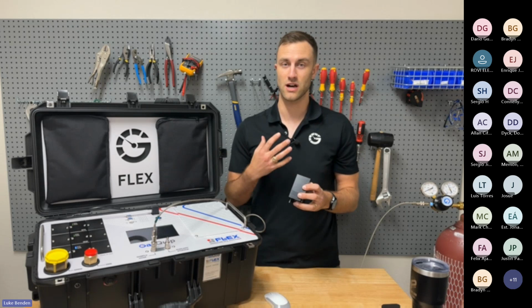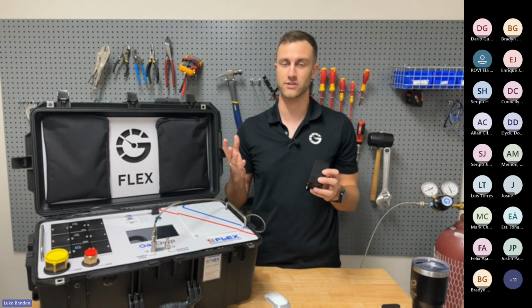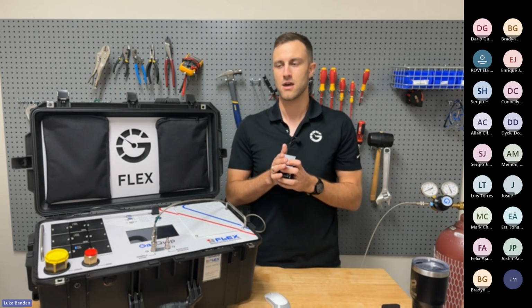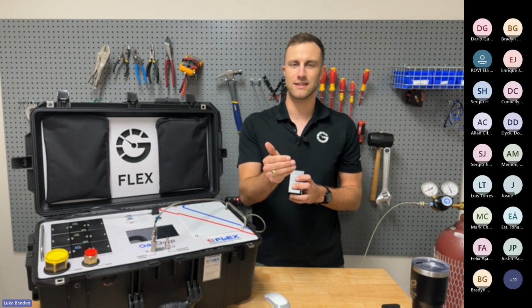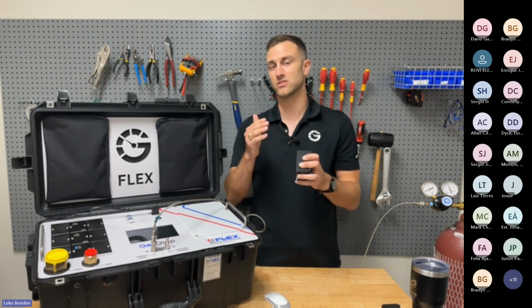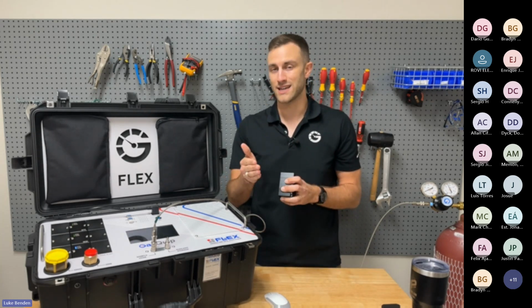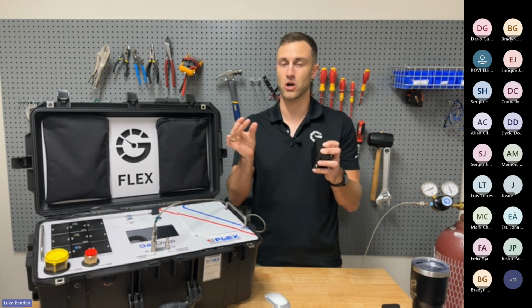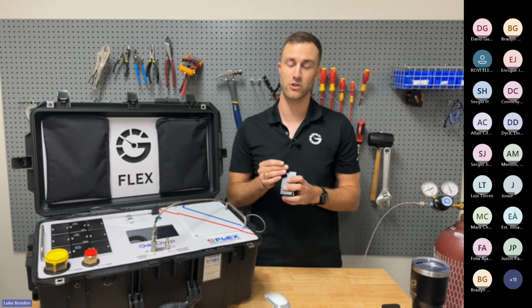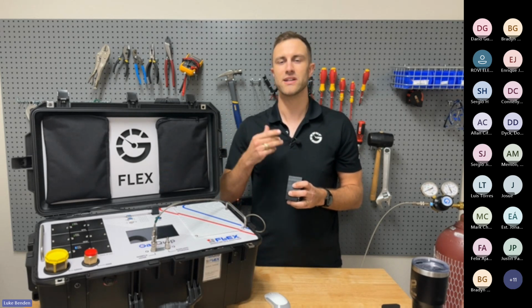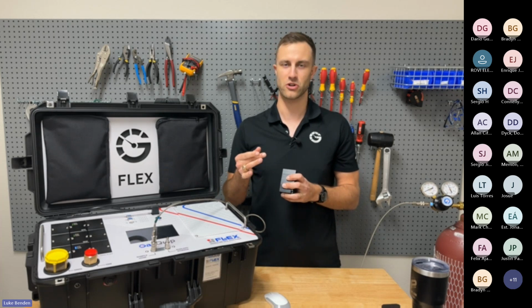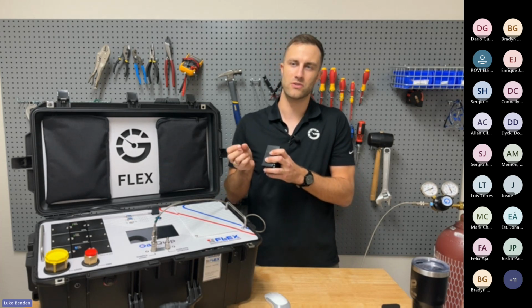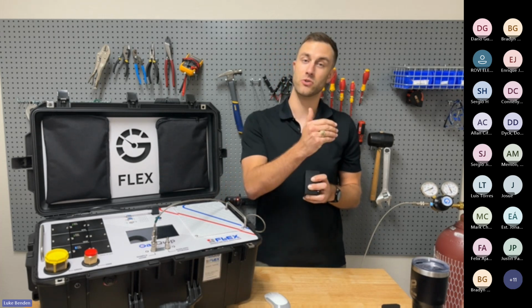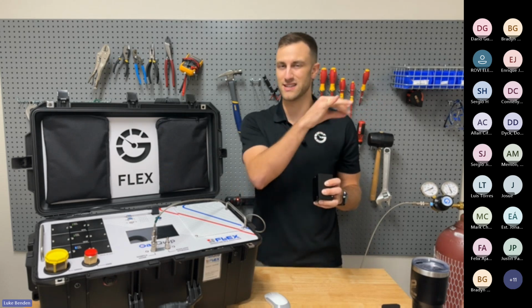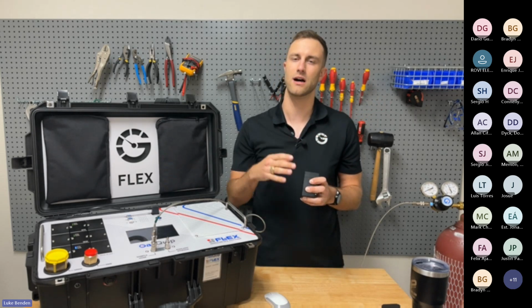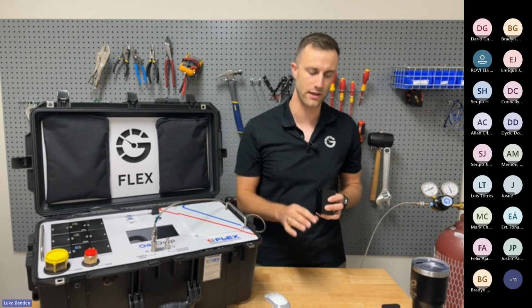And that's unique to us. That's the first time it's been done in an analyzer. The reason that we did that is that if you've been out in the field testing gas, you notice sometimes that it takes 2, maybe 3 tests before your values really start to hone in and get where you need to go, especially on the moisture. So heating up that sensor to burn off that residual moisture is a way to not have to run 2 to 3 samples to pass gas over it and desiccate out the sensors. You can just heat it up and start from a clean slate.